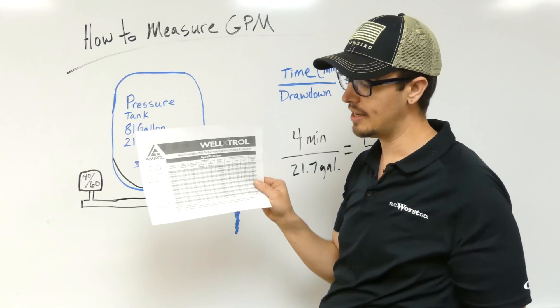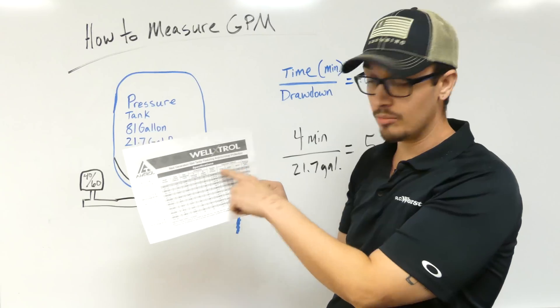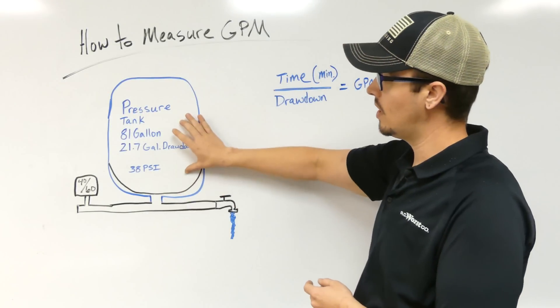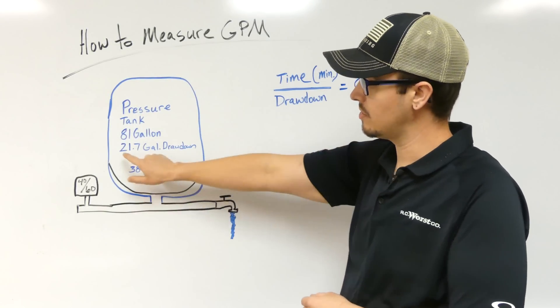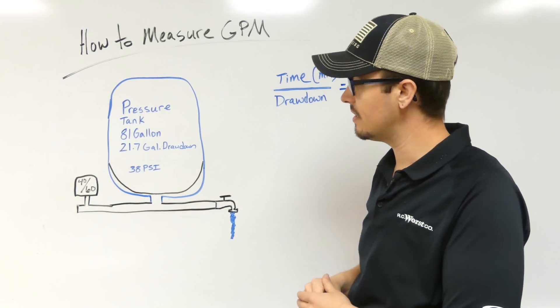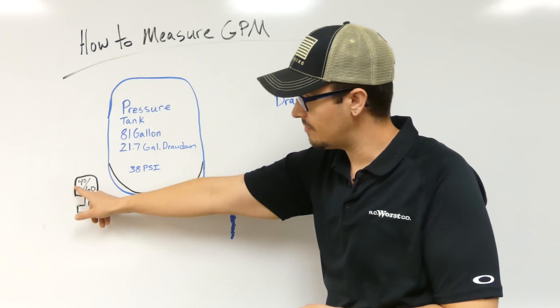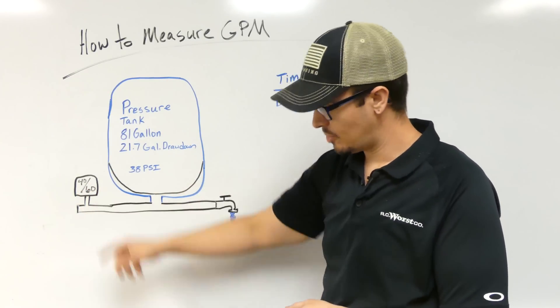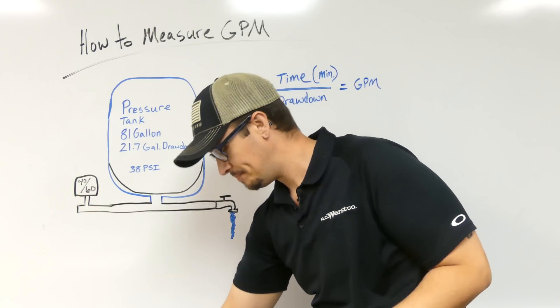It gives you a generic idea of what your drawdown is going to be at the different pressure ratings. So this would be a Well-X-Trol tank in this example. You have a 21.7 gallon drawdown on a 40 to 60. This is my pressure switch.